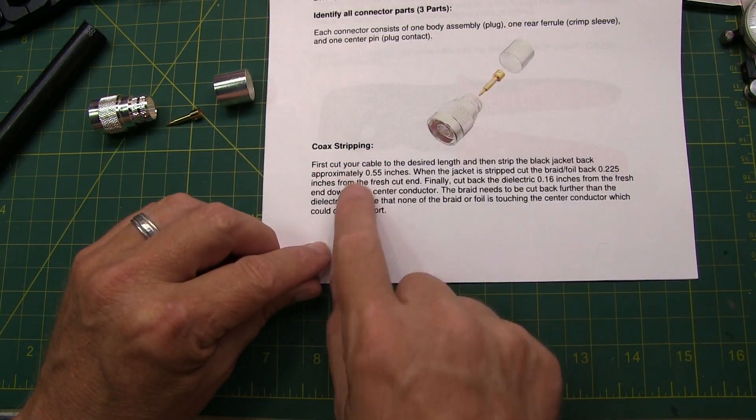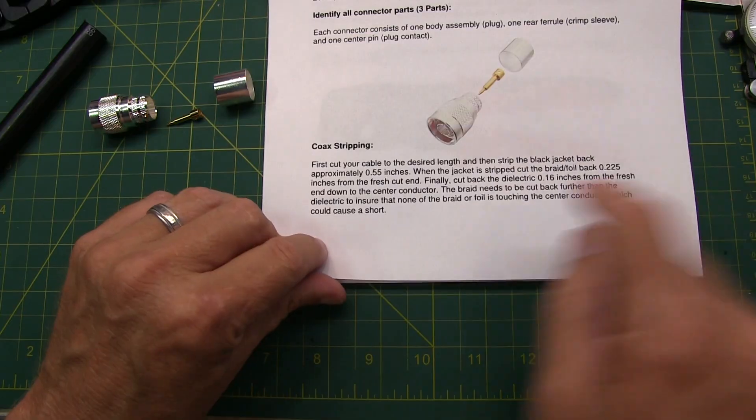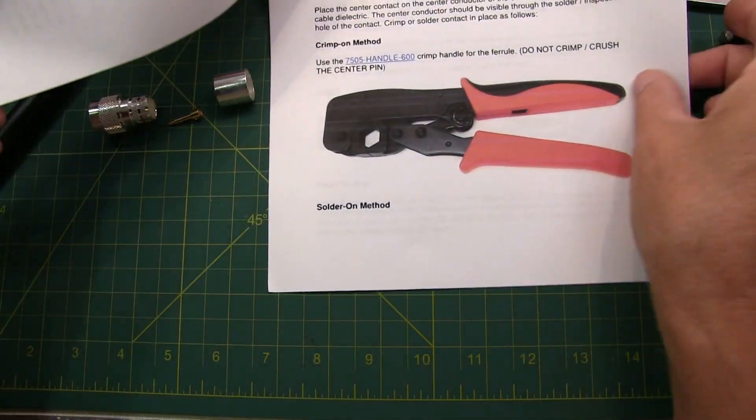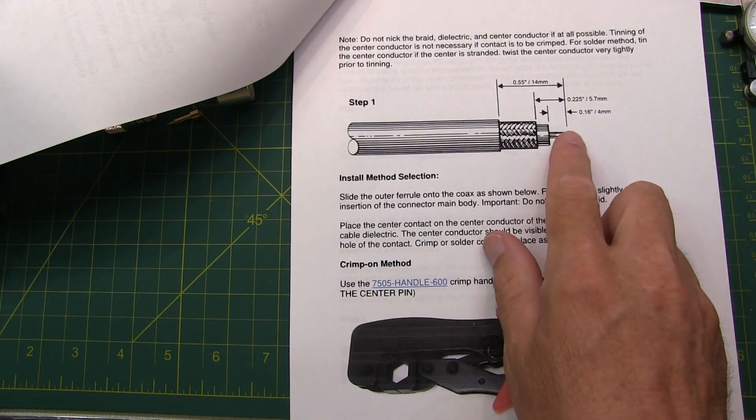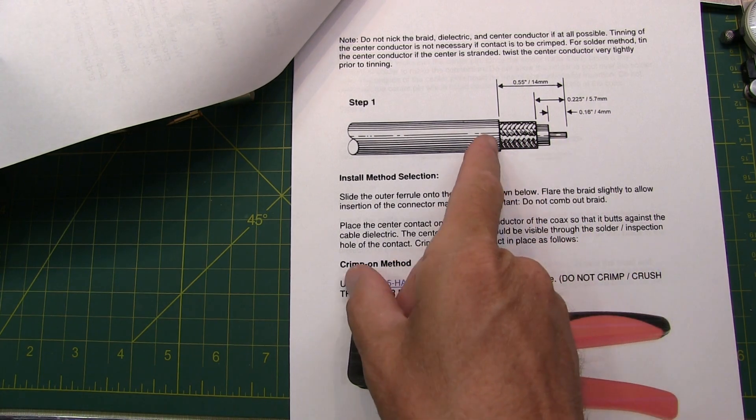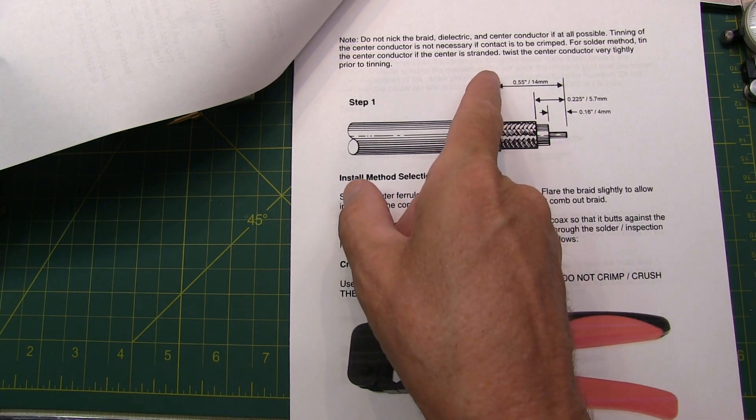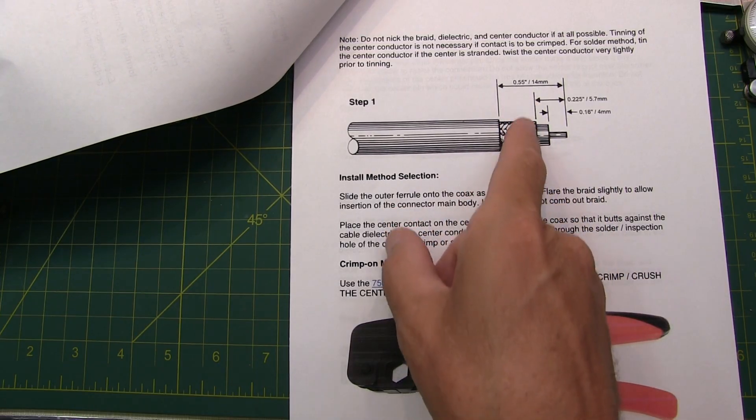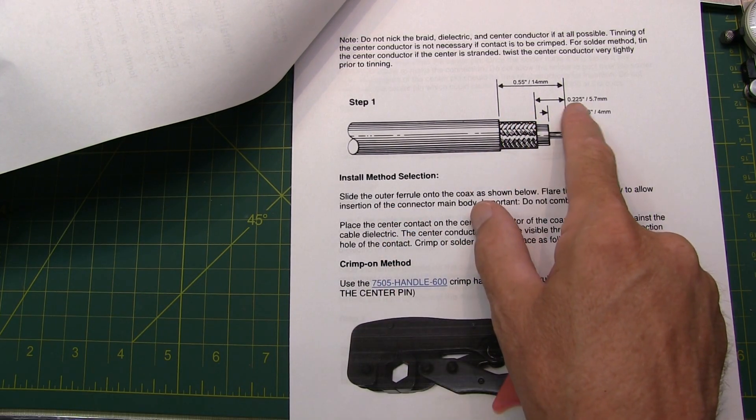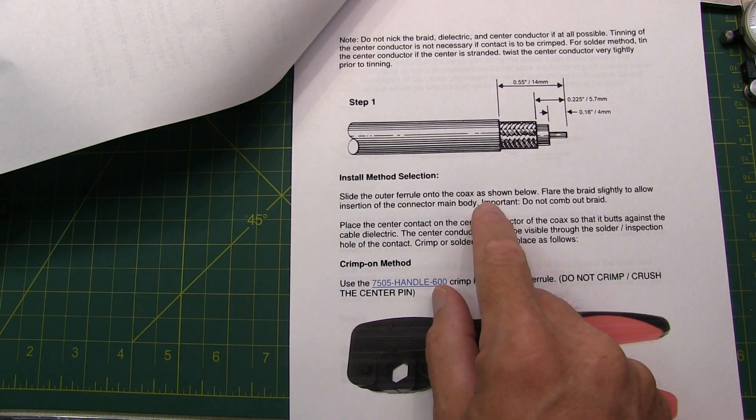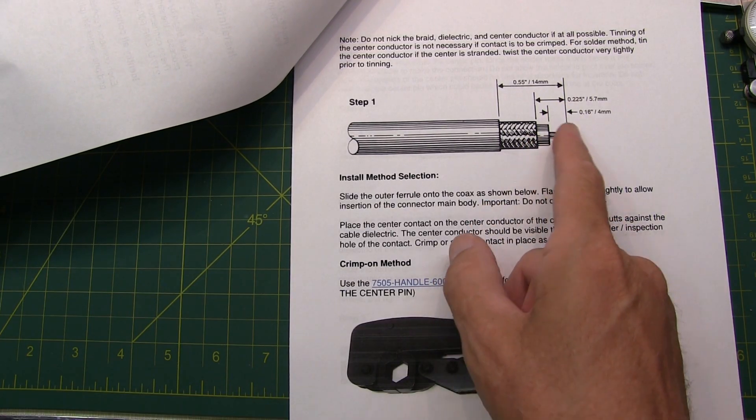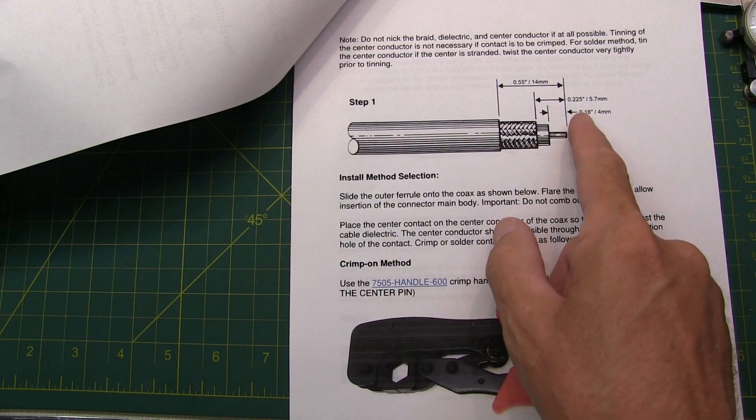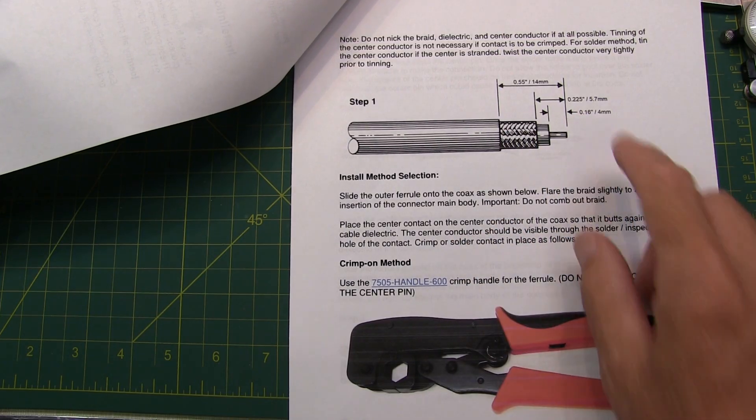The installation guide includes a coax stripping guide which is spelled out here and then shown in this diagram. I'm going to strip back the main insulation just a little over half an inch, 0.55 inches, then strip back the shielding just under a quarter of an inch or 0.225 inches, and then strip back to the center conductor about 0.16 inches or about 4 millimeters.